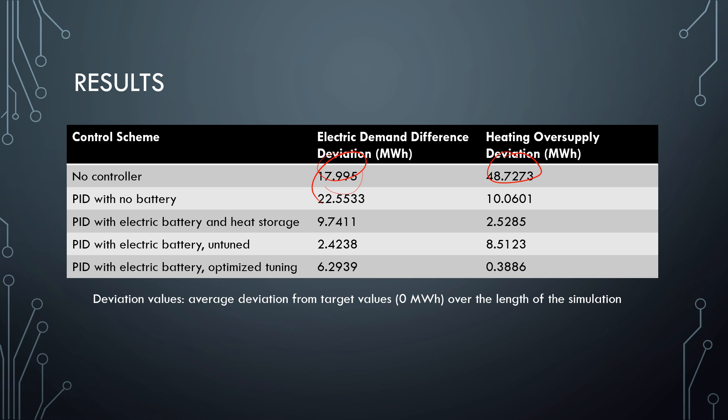With no battery, we actually had a worse deviation on the electric demand, but it improved the heating quite a bit. When we had both types of storage — both electric and heat storage — both deviations improved. But by far the best system was two PID controllers, one for heat and one for electric, with optimized tuning and the electric battery but no heat storage device.